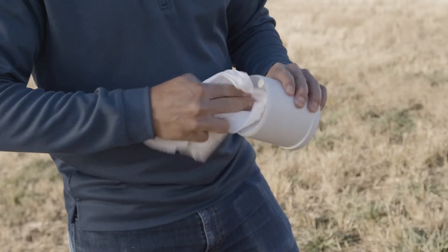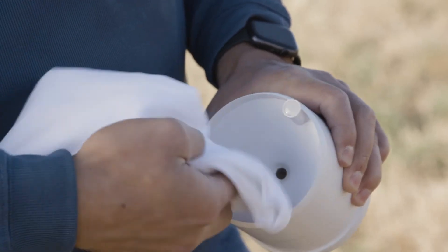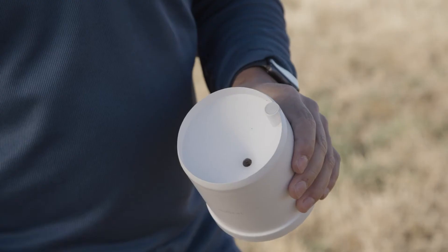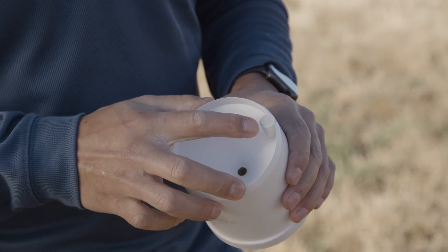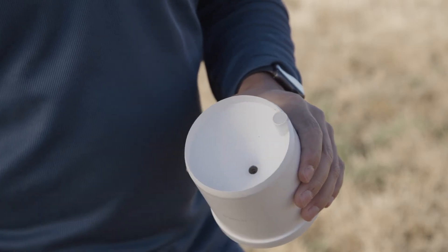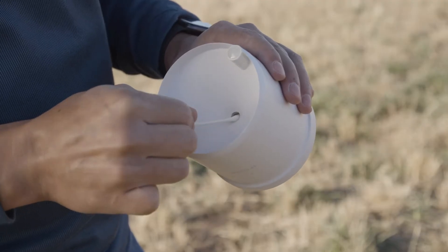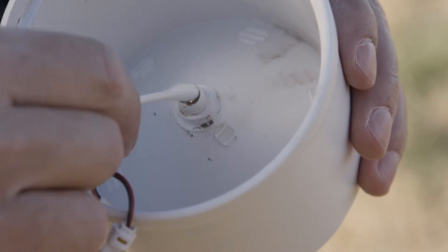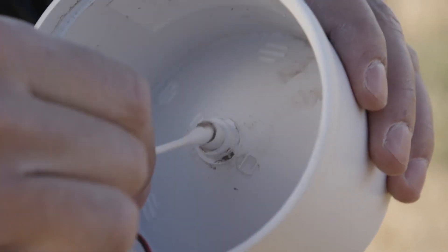Use a clean, damp cloth to wipe out the funnel. Clear out all dust and debris. Be careful not to wipe the pyranometer sensor with an abrasive cloth. Then, use a cleaning swab to clean the funnel hole. The swab should be small enough to go inside the hole to clean out debris.